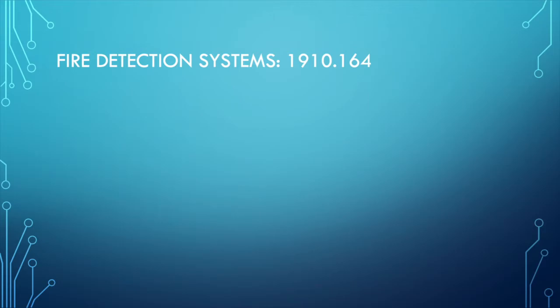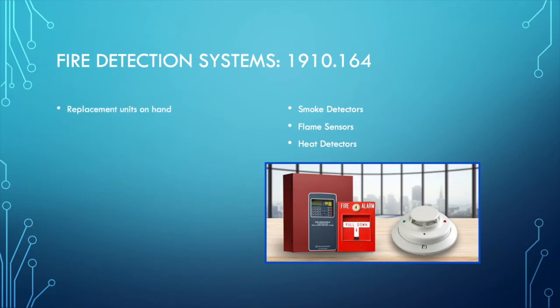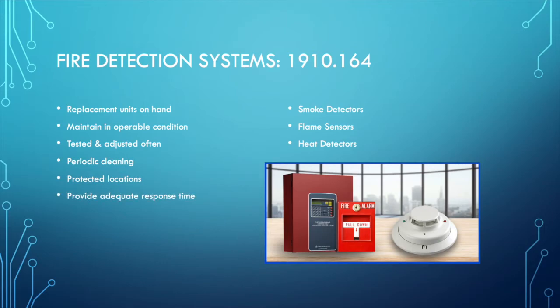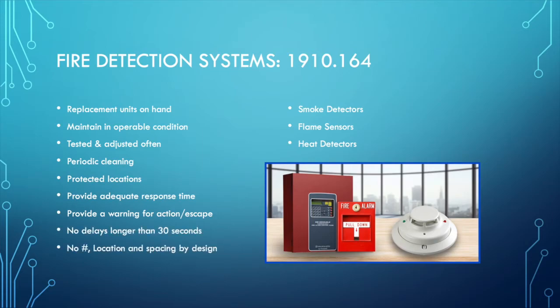Fire Detection Systems, 1910.164. These types of detection systems include smoke detectors, flame sensors, and heat detectors. They need to have replacement units on hand, be maintained in operable condition, tested and adjusted often, with periodic cleaning of systems, protected locations, provide adequate response time, provide a warning for action and escape, no delays longer than 30 seconds, number, location, and spacing by design.